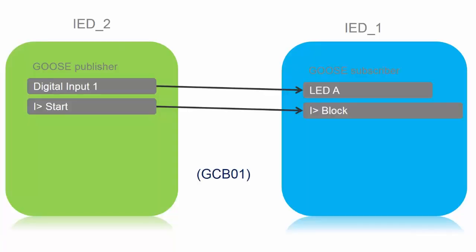We will configure object 1 control and status and first stage overcurrent protection as a buffered report control block to the client. We will define another device IED_2 to publish two GOOSE signals, one is the digital input and the other one is overcurrent first stage activation, and we will use those GOOSE signals for digital input to activate an LED on the front and for the overcurrent stage we will use it to block the overcurrent stage of the upstream relay IED_1.